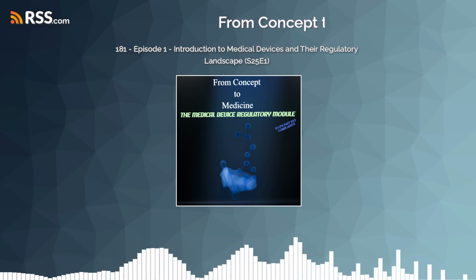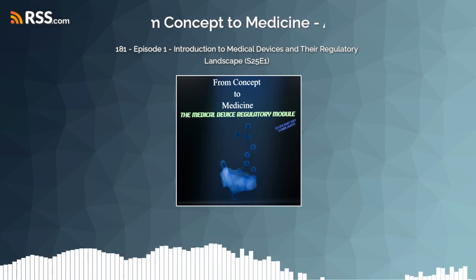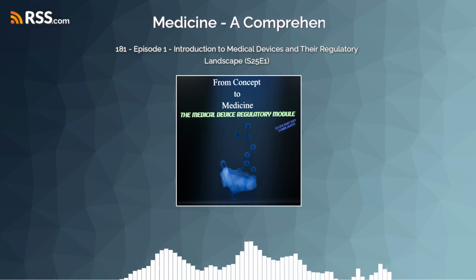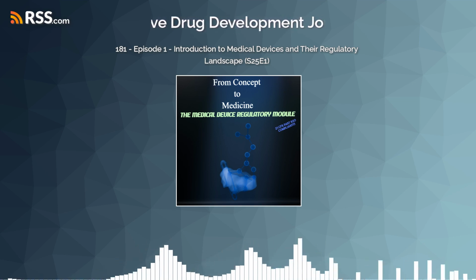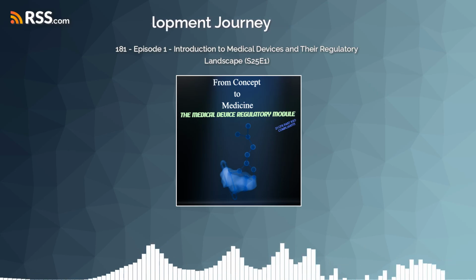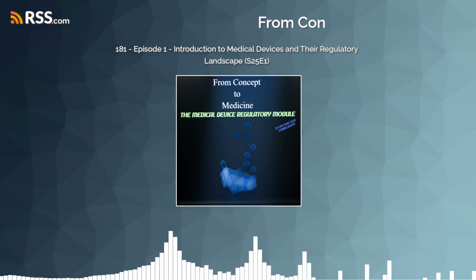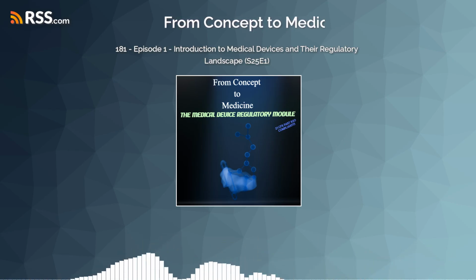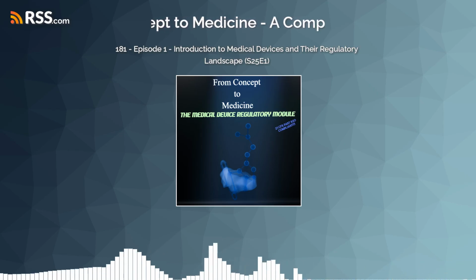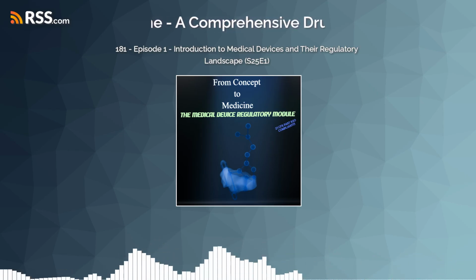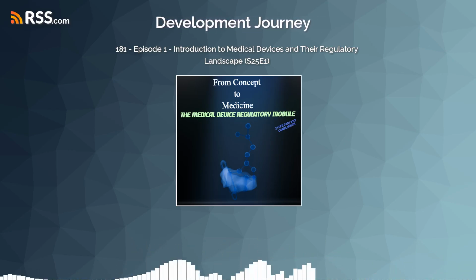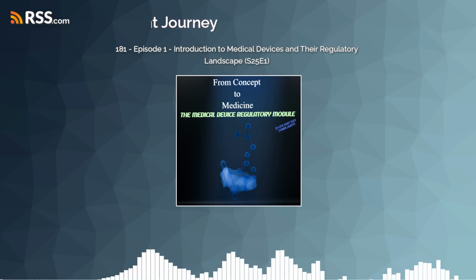That's thorough. Okay, what about the labeling and packaging, the part the user actually sees? Are there strict QSR rules for that too? Absolutely. Labeling and packaging fall under the QSR and also have their own specific regulation, 21 CFR Part 801. Labels need adequate directions for use, warnings, contraindications, and so on. Clear information. Yes, and they must comply with the Unique Device Identification, or UDI, rules for traceability throughout the supply chain. Labels have to be legible, securely affixed, and meticulously inspected for accuracy before any device is released for distribution. It's a critical control point. UDI for traceability. Makes sense.